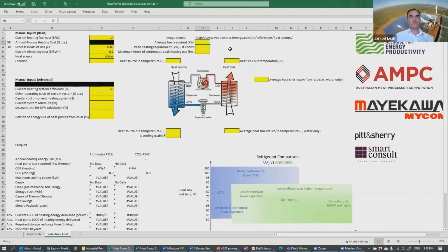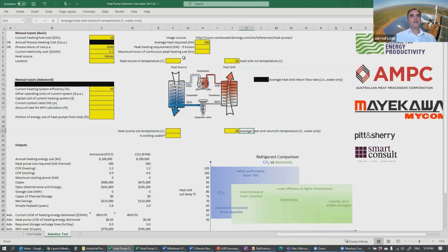Then you move on to sizing of the actual equipment, entering, let's say, the size of the heat you require is 500 kilowatts, and you require heating for your sterilization water at say 82 degrees. This may be returning from a factory or from freshwater feed—let's say that's coming in at 60 degrees. Then, let's assume you're using hot water from your refrigeration plant at, let's call that 25 degrees. This cooling is useful, and we'll take that down to 15 degrees.